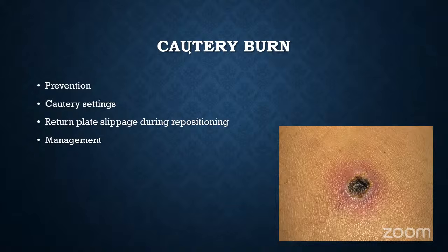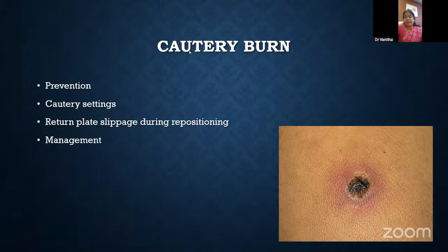Most of the time, freelance laparoscopic surgeons, we have this problem because we operate in different theaters where the generators also are different types. The recent generators have isolated units where the current doesn't even flow when the return plate is not properly placed. But with the older ones, when you try to operate with the monopolar and keep trying and you don't get the current flow, that's a time where you really cannot keep increasing the setting. You need to really think whether the return is going properly. So these are all things.